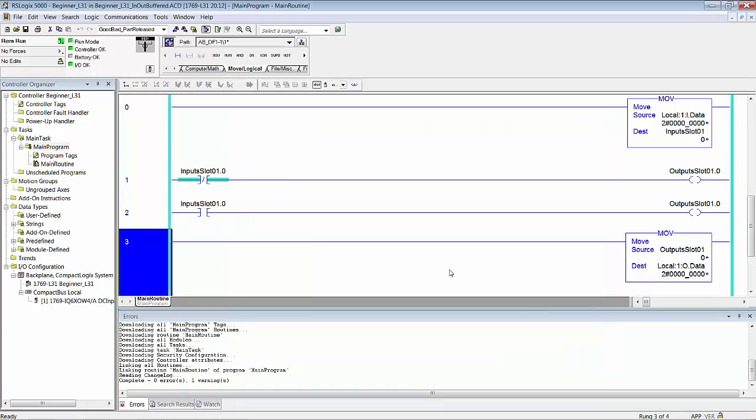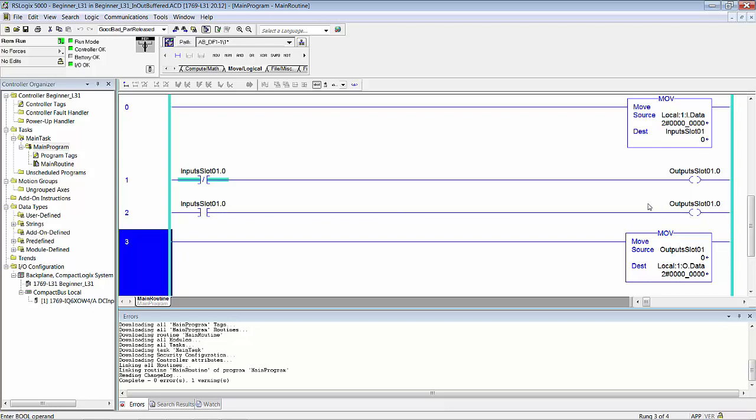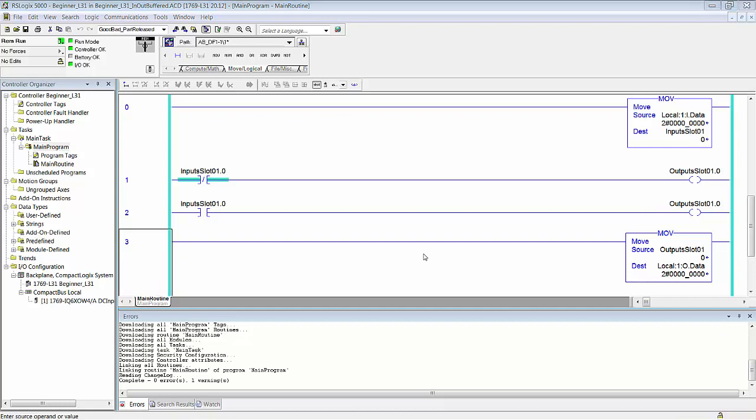Okay, here we are back in the run mode and notice that everything is nice and quiet. Last man wins. This rung says it's on, this rung says it's off. Last man wins. So right after this, this bit is turned on and turned off. This bit is actually turned on. At the end of this rung when this rung is scanned it turns that bit on, and then within 10 microseconds it reads this rung and turns it right back off. That rung—oh, there I just saw it flicker. If you have your thinking cap on and you're really pondering this situation, then you can see that this is much more stable.